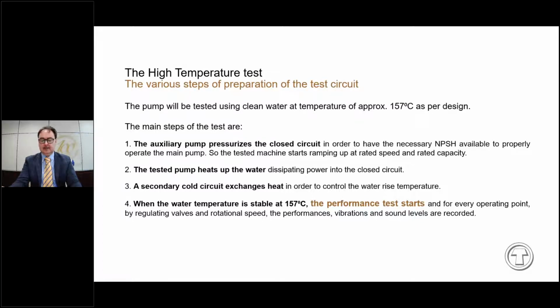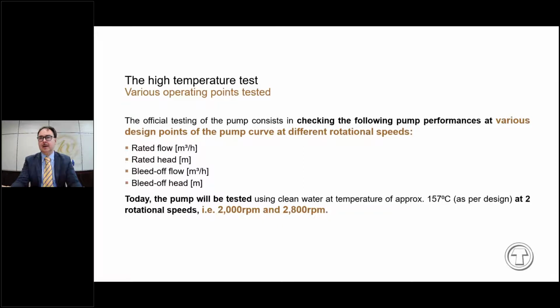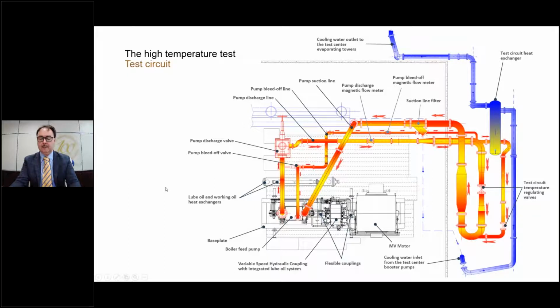As we show in the next slide, today we will check the rated flow and rated head, and the bleed off flow and bleed off head, at 2 different rotational speeds, that is 2000 RPM and 2800 RPM, which are velocities close to the boundary limits of the operation of the hydraulic coupling. Before I hand it over to my colleagues of the test room, we briefly go into the detail of the test circuit. The test circuit is depicted at the bottom left: the pump skid with, on the left, the pump, in the middle the hydraulic coupling, and the electric motor.